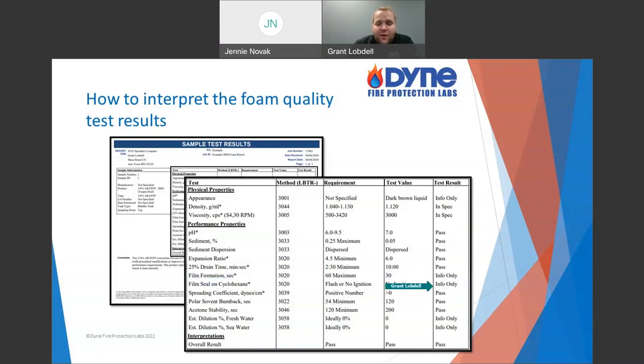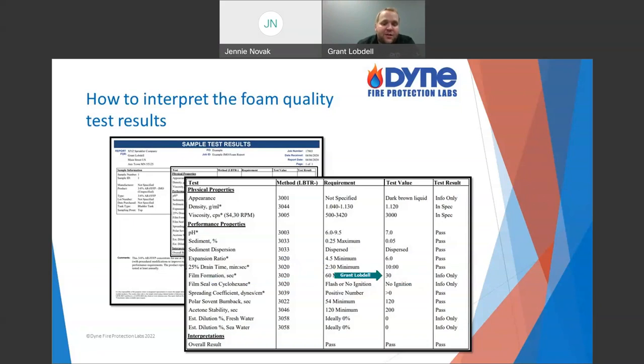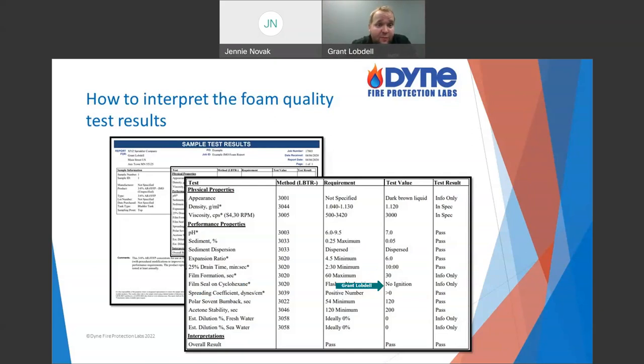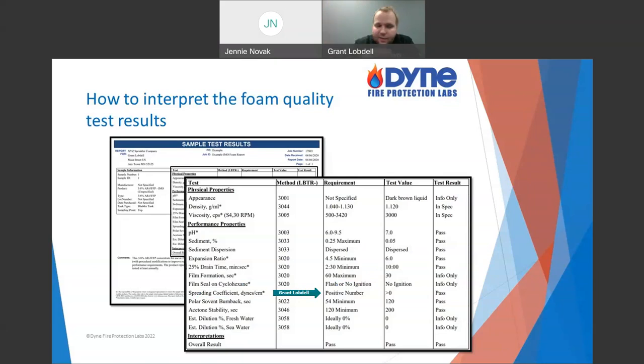For drain time: why is it low? Again, dilution, age, storage conditions, things breaking down, contamination, or accelerated reactions due to poor storage. For film formation: we provide info only, doing it a bit more technically than just a dollop — we apply a specific amount of solution on a surface area, then pass a match over it and see how long it takes to form a film and whether that film prevents ignition. If it formed a film, it won't ignite; if it didn't, it would. For spreading coefficient: it just needs to be greater than zero — positive means film-forming. The ones on the edge, we take and do the actual spreading coefficient measurement.